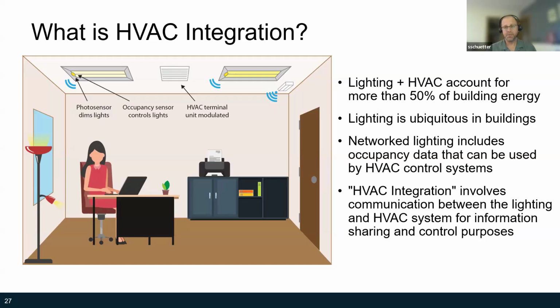not being used. Today, we're more focused not on an unoccupied period overnight, but on short unoccupied periods during the day. Since lighting is everywhere, luminaire level controls in the lighting can be leveraged to not only dim the lights, but also control the HVAC temperature set points when occupants leave the room. Integrating lighting and HVAC also gives a facility visibility and the ability to control the 2 largest energy consumers. So essentially, we're taking all the occupancy data that the lighting system is collecting and using it to more optimally control the HVAC.